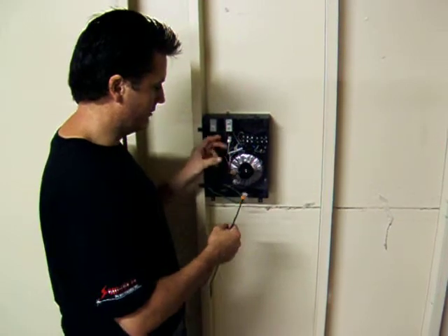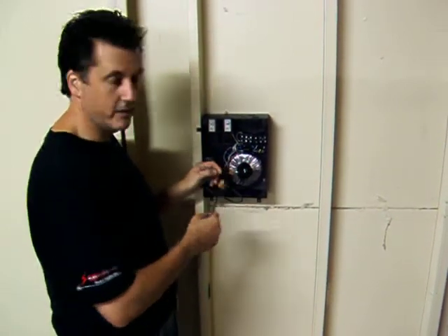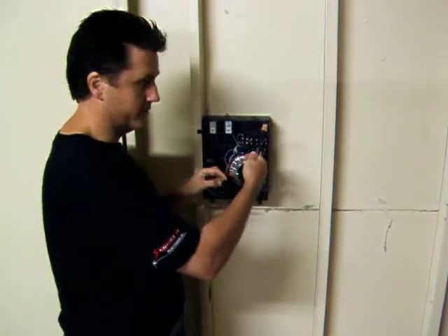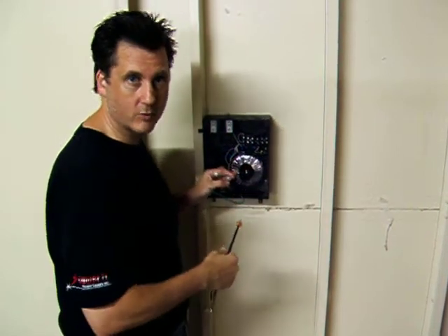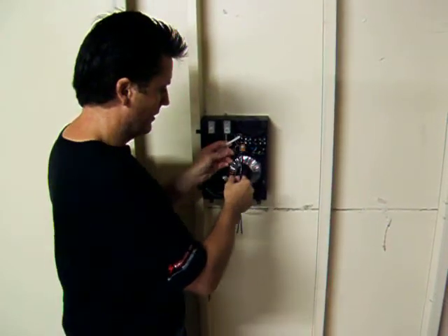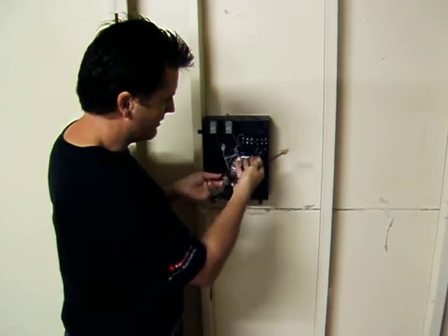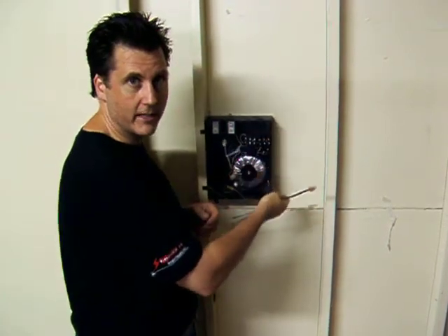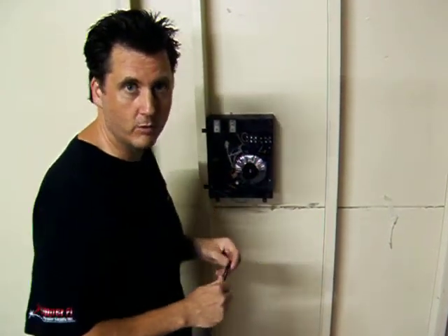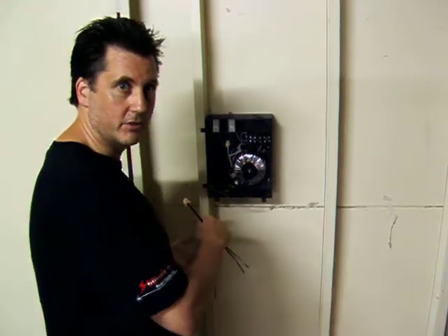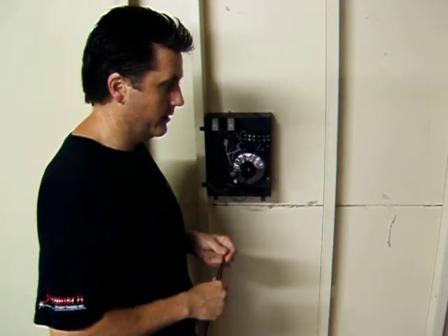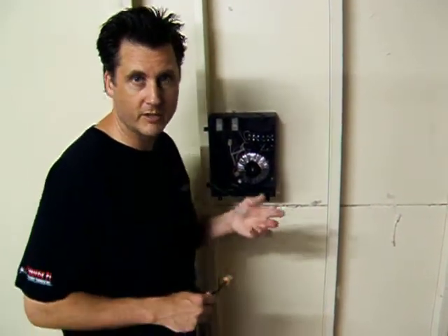So when you receive 120 volts into the white and the black, you'll get 12 volts, or 24 volts if it's set up for 24 volts on the output. The yellow tap will raise the voltage on all the secondary taps up approximately 1 volt, to compensate for 10 volts of loss on the primary. The amount of boost you're going to get is really dependent upon what your actual input is, and since a transformer is an unregulated device, it could fluctuate depending on load, job, etc.